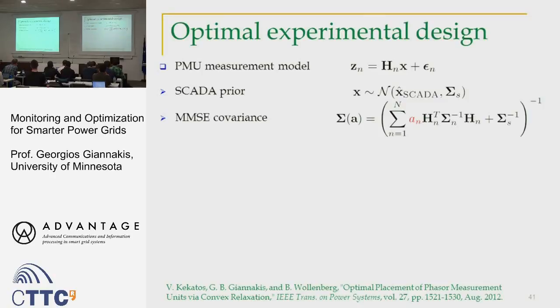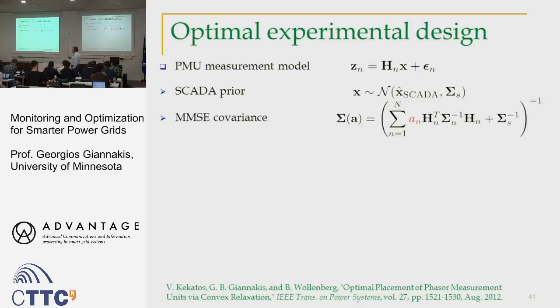We designate a vector a_n, called the assignment vector. For every node n, a_n takes the value 0 or 1. If a_n equals 1, you place a PMU at that bus; if 0, you do not install it. The covariance of the estimator X given this prior is given by the corresponding expression. When the prior term is zero, this reduces to the standard least squares covariance matrix. This formulation also utilizes the SCADA measurements as a prior.